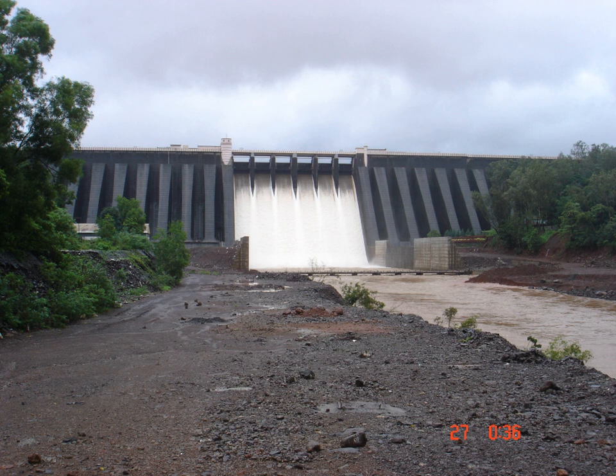Initially a weir was proposed to divert the water coming out of the tail race tunnel of Stage 1 and 2, but it was later observed that the water still had a hydraulic head of about 120 m which could be used. To use this head, the Kolkawadi Dam was constructed at this location. It forms a balancing reservoir and maintains the head. This dam impounds the tail race water from Stage 1 and 2, and this water is drawn through penstocks and electricity is generated by four Francis turbine units with a capacity of 80 MW each. The tail race water from these stages then flows through a channel and joins the Arabian Sea near Chiplun. The installed generating capacity of this stage is 320 MW.